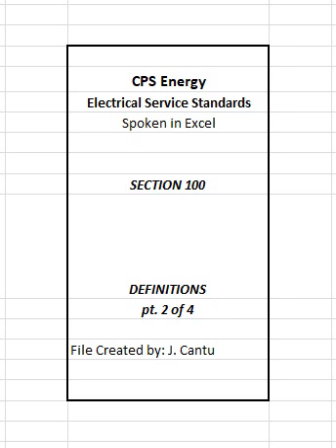A service-rated disconnect furnished and installed by customer on their premises that will be used by CPS Energy to disconnect the customer's secondary service conductors from the downtown network system. The grid-tied disconnect shall be under the exclusive control of CPS Energy and remain locked and sealed by CPS Energy personnel at all times. Grid-tied fuse pad.